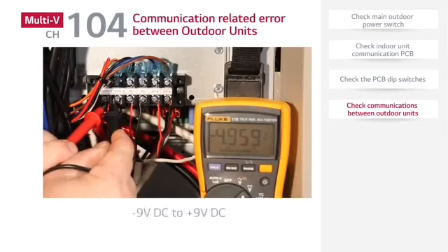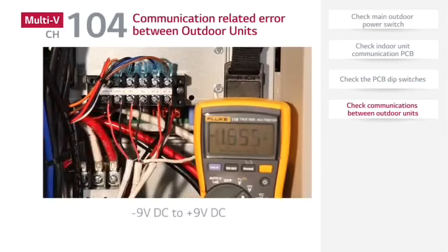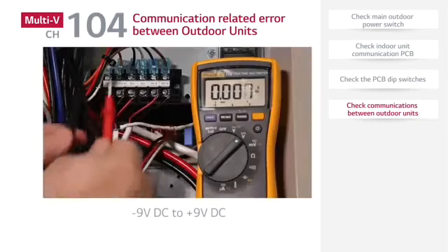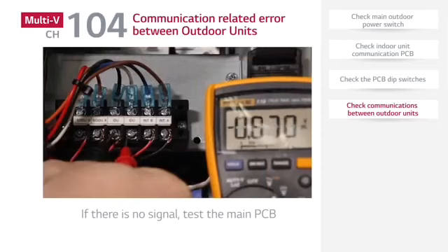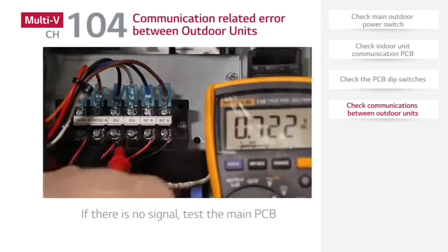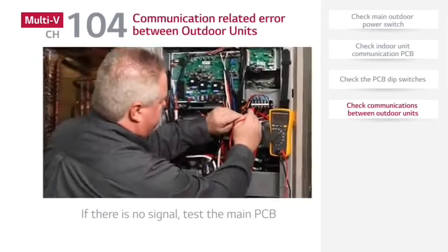The normal voltage value for the communication signal between outdoor units should vary from minus 9 volts DC to plus 9 volts DC. If there is no signal, test the main PCB. If there is still no signal, replace the main PCB.